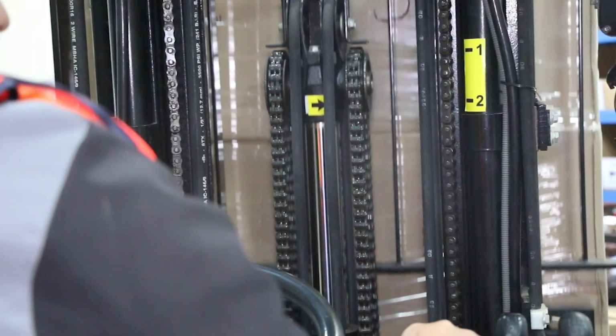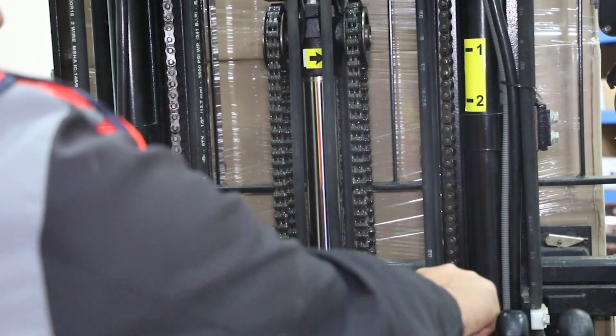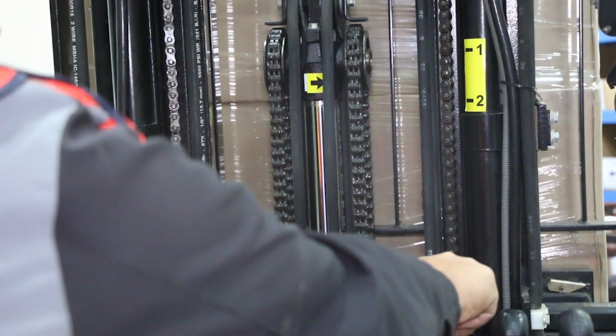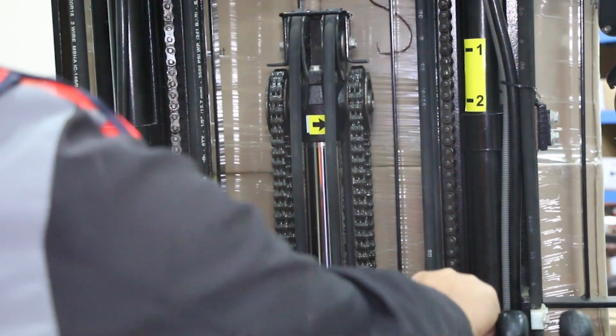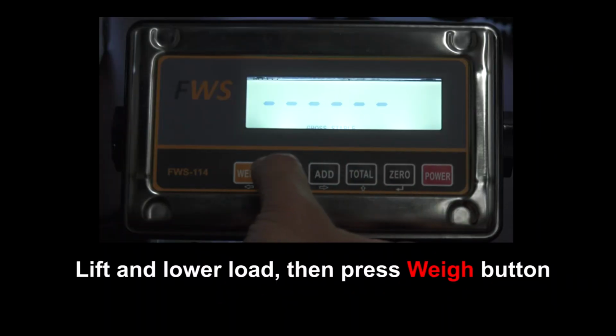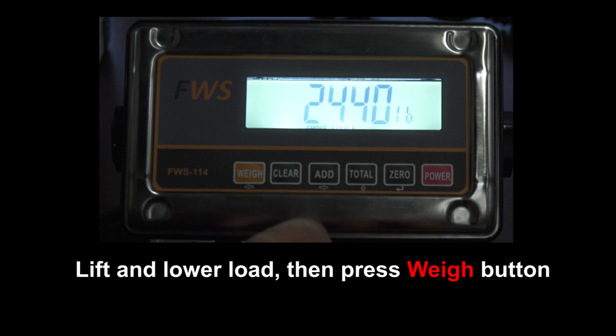To test to make sure that the calibration has worked successfully, you can now weigh your load, again raising to the number 1 decal, lowering to the number 2 decal, and hitting weigh. You should get a value that's extremely close to the test weight.